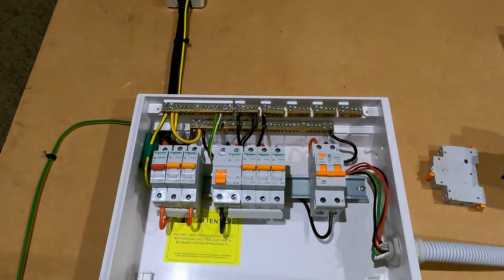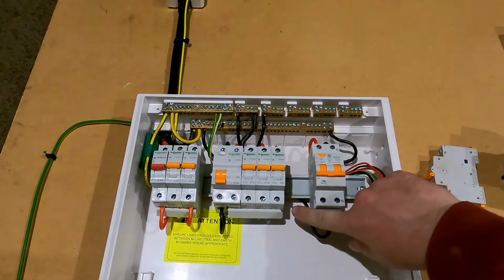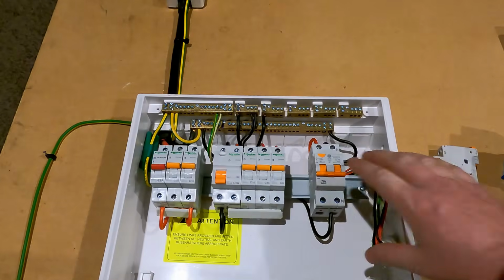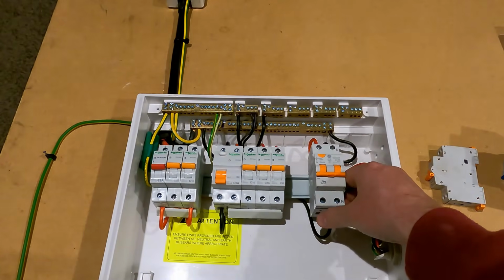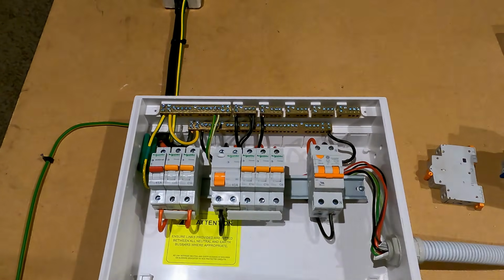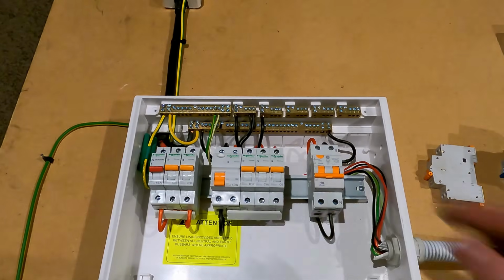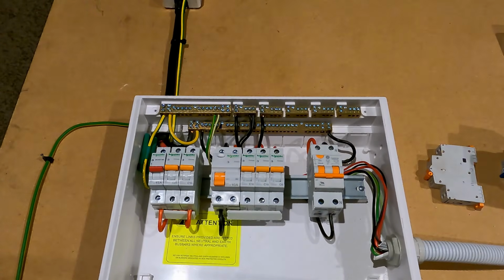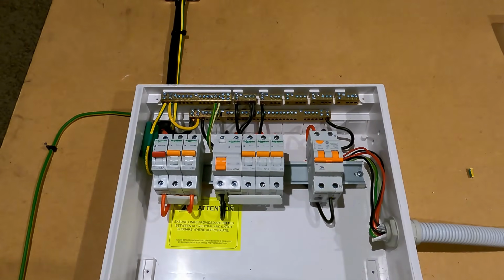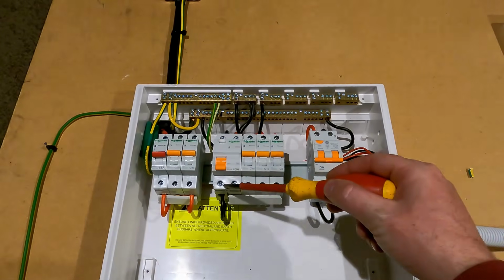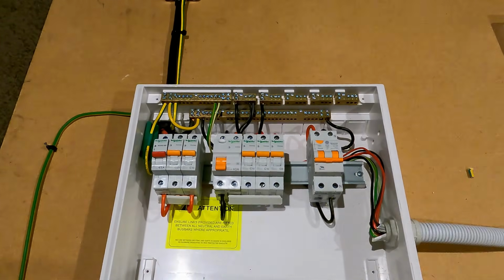Sweet as. So what I've done there, just replace that bar, put that neutral in properly, and then change that block out for the RCBO. Wicked. When you throw these in, make sure you crank them up a bit with a big flat head or a proper circuit breaker screwdriver, not just a posi or small flat head. Now what we want to go around and check is that every single terminal is tight and done up properly.